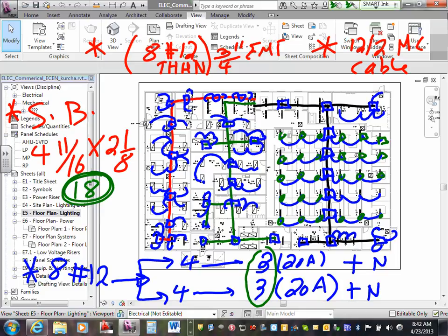So it allows you for future expansion, guys, to pull the conductors from here all the way to any of these boxes. Then, Jeff, you come over there and you tie to any expansion that you need in the ceiling. We're still going to do the multi-wire branch circuit. That isn't very common anywhere. We're using multi-wire branch circuit. If you guys want to use it now, good point. What if I don't want to use a multi-wire branch circuit?